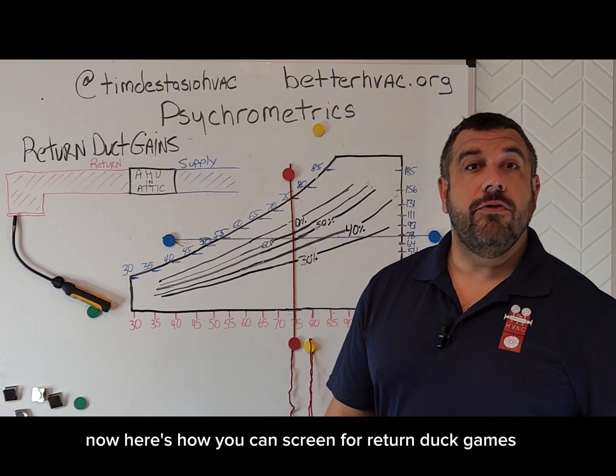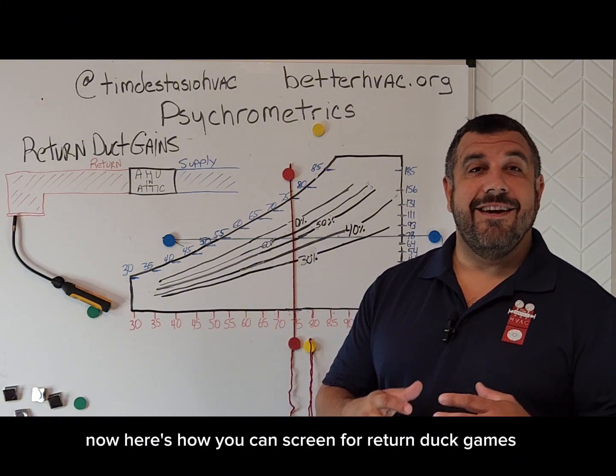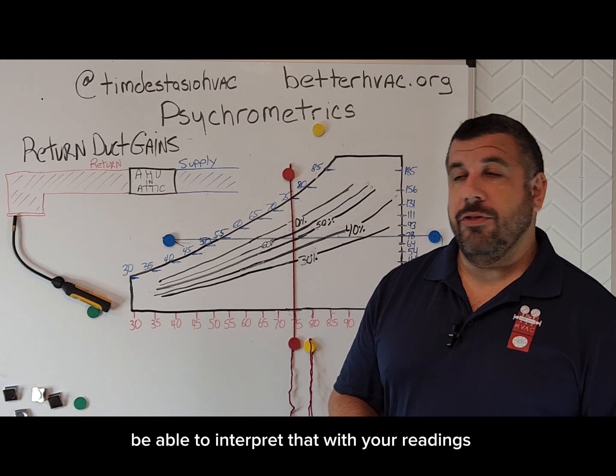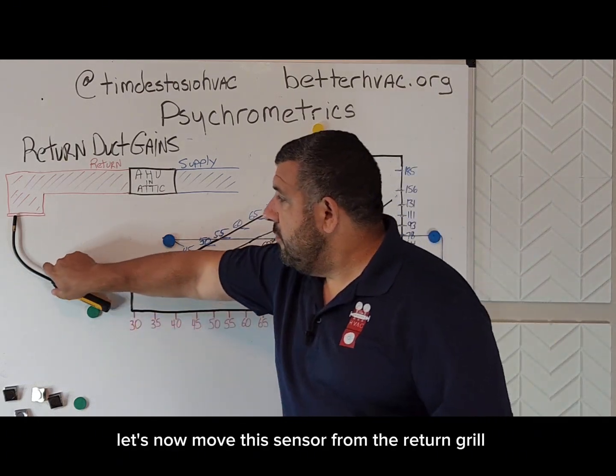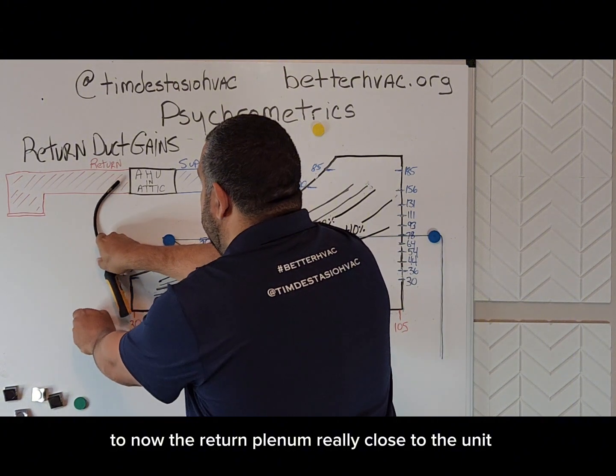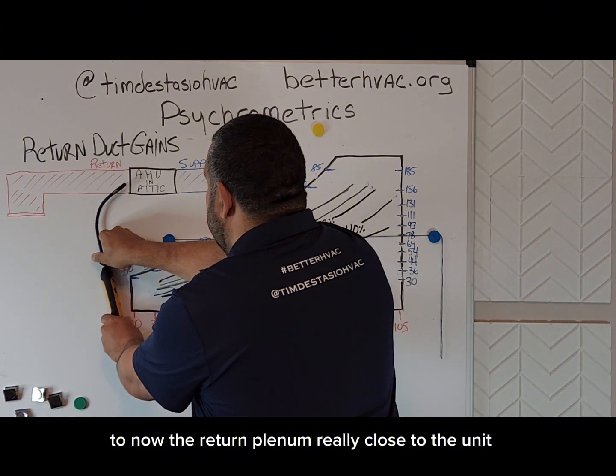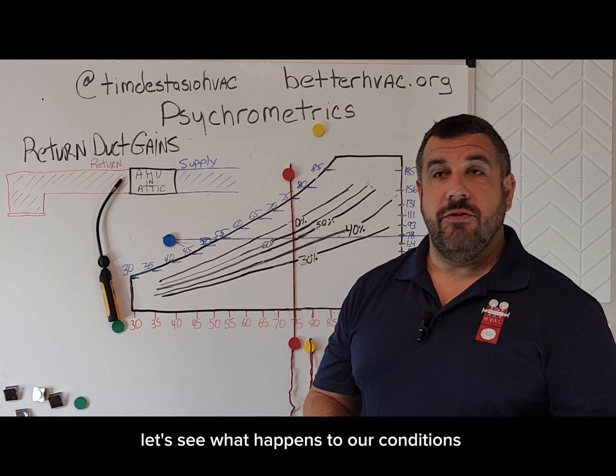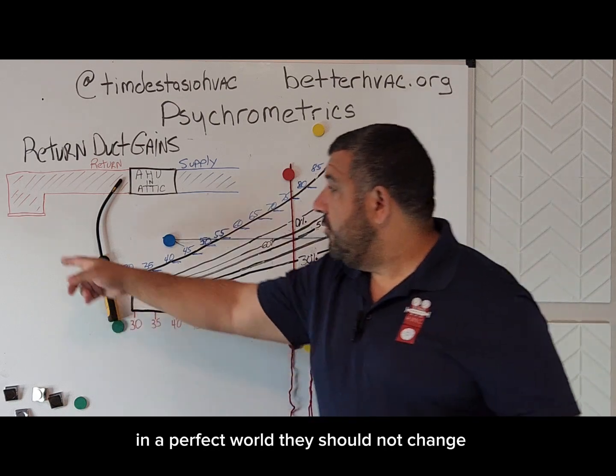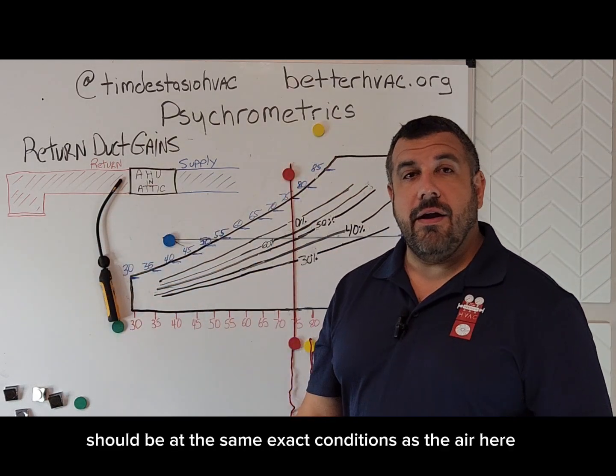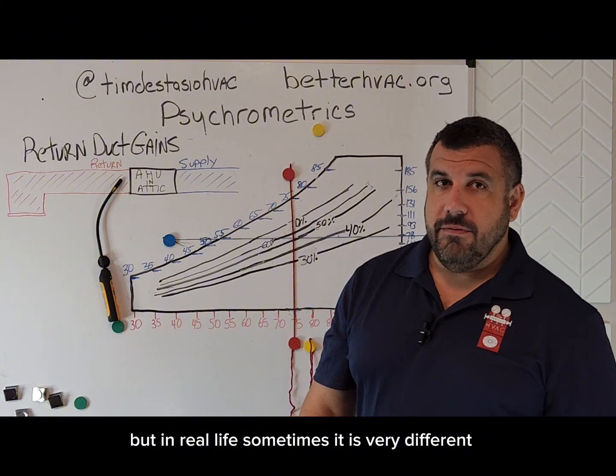Now, here's how you can screen for return duct gains and be able to interpret that with your readings. Let's now move this sensor from the return grille to now the return plenum really close to the unit. Let's see what happens to our conditions. In a perfect world, they should not change. The air coming in here should be at the same exact conditions as the air here, but in real life, sometimes it is very different.